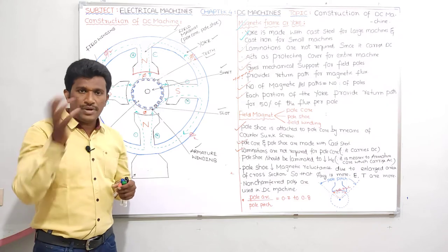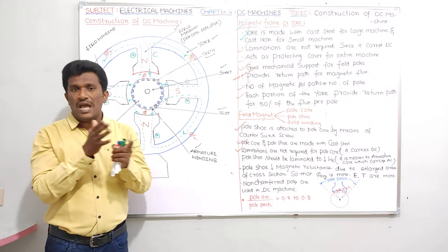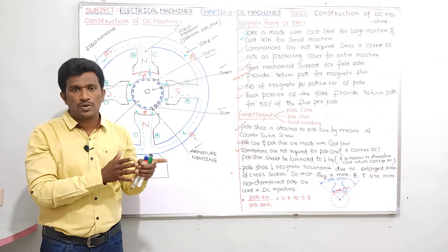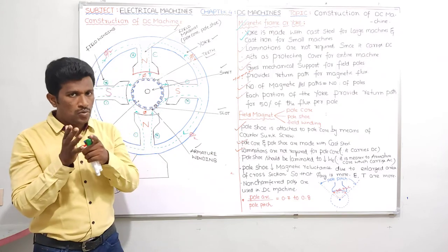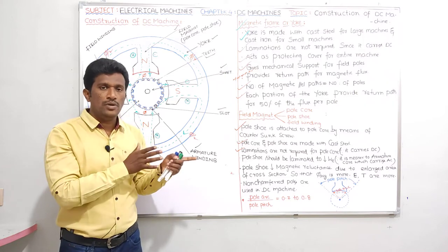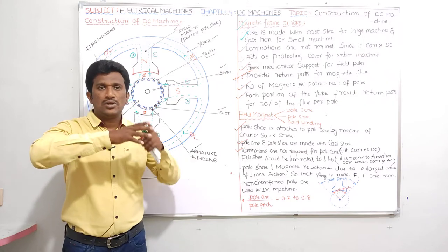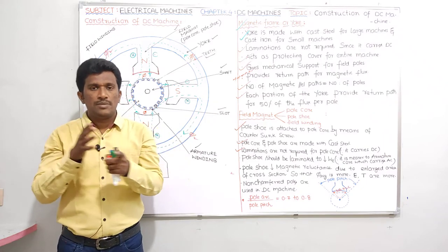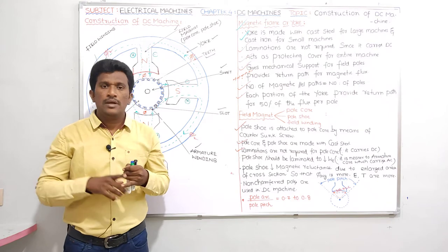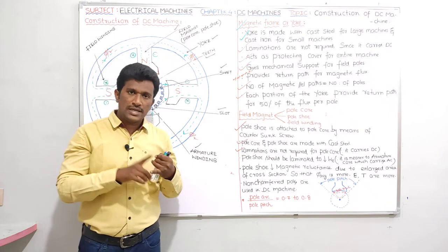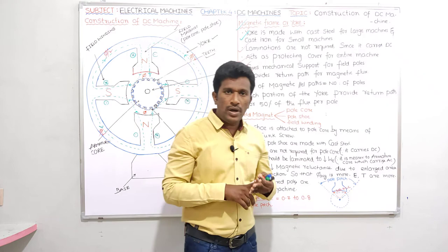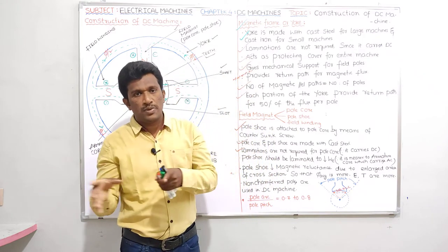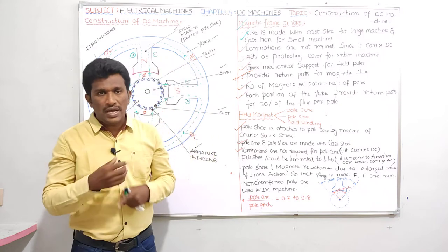So how do we provide laminations? Between the layers of laminations, we have to provide some insulating material. All those things I explained in the transformer core. Those who did not watch the transformer videos, you can watch that video. There I clearly explained that the transformer core is built from a number of layers of laminations separated by insulating materials like red oxide, China clay, Japan varnish. There are so many insulating materials.